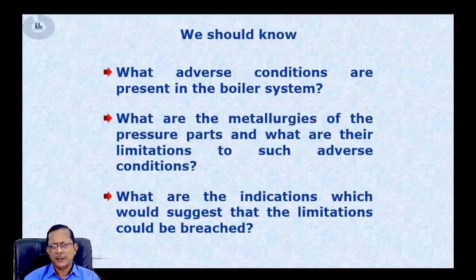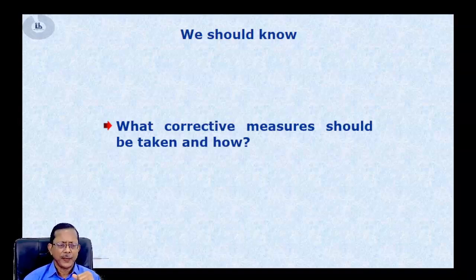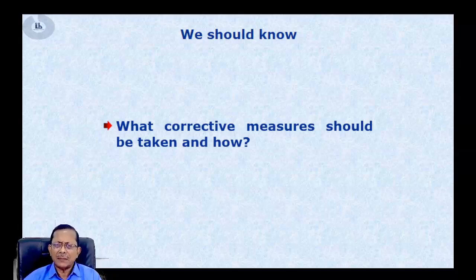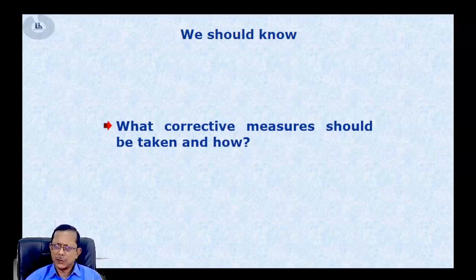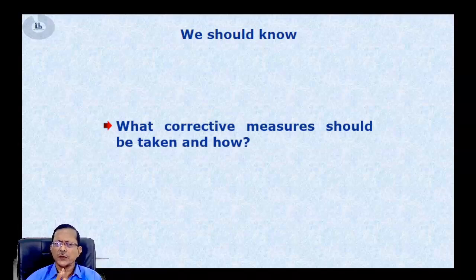We should definitely know what corrective actions are required. For example, if there is an overheating failure because of high gas temperature, and that high gas temperature in the upper furnace zone is because of delayed combustion, then in order to remove the cause I need to control the delayed combustion condition and bring the combustion to the right zone. That is the corrective measure, and I should know how to implement it.